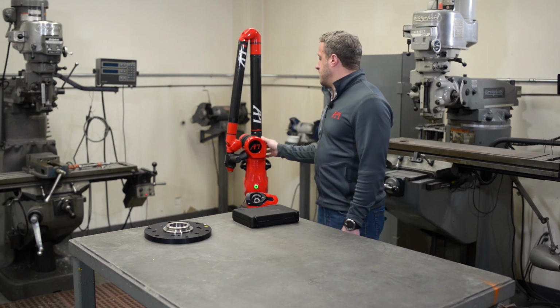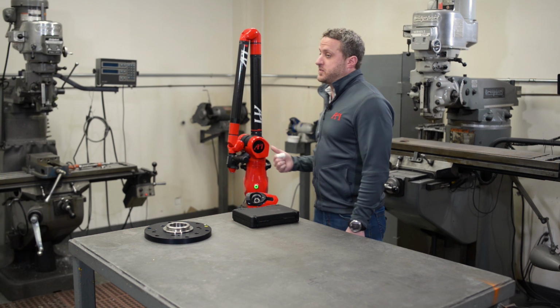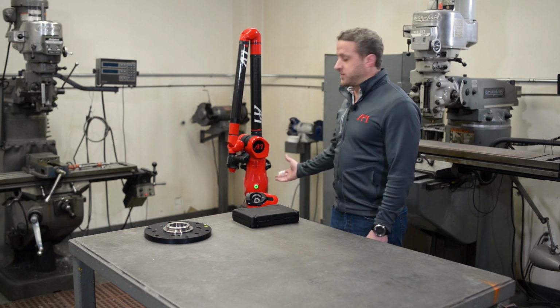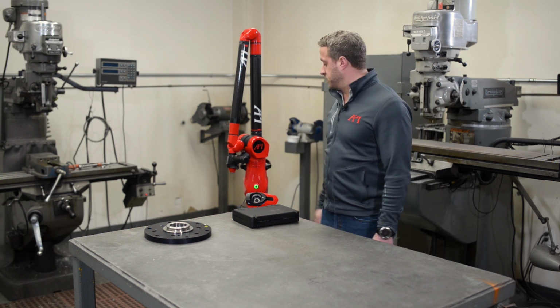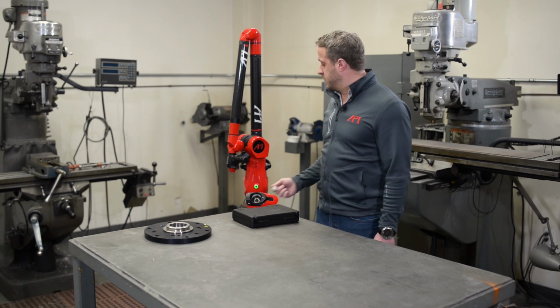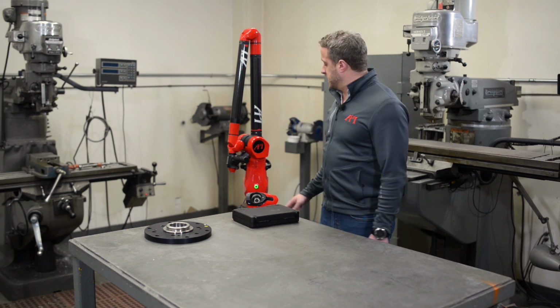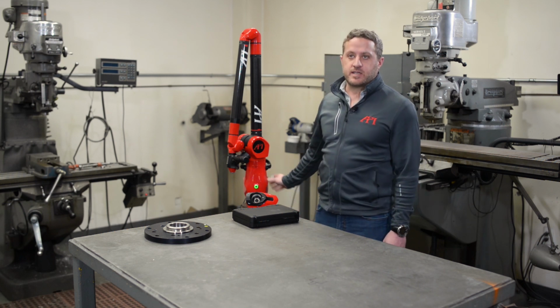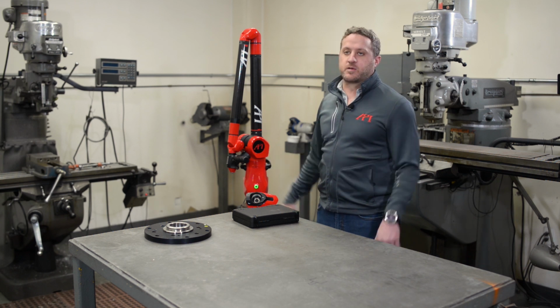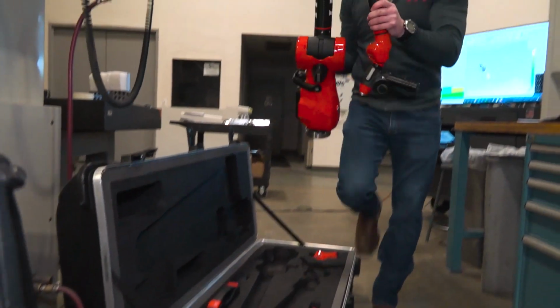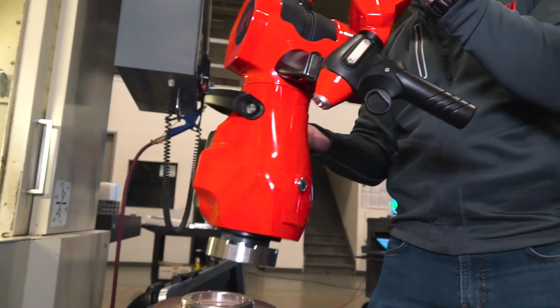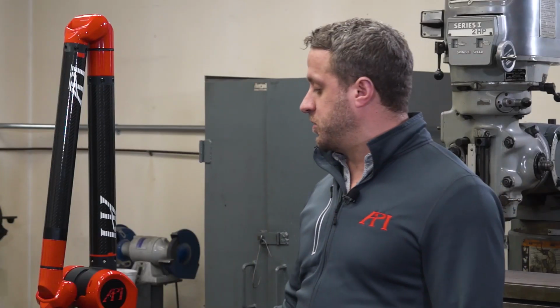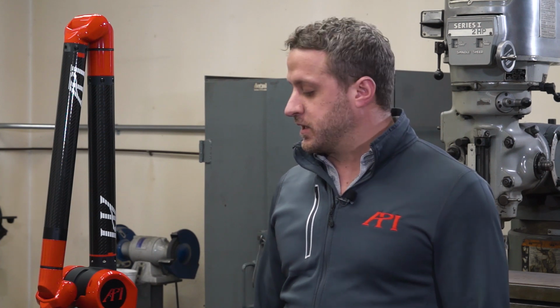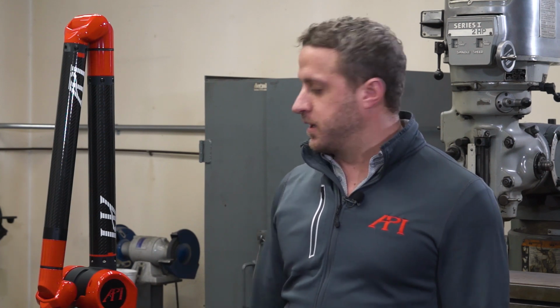This arm has pretty nice features as far as the portability of it. This has a battery pack on the back that can give you several hours of working with no power plugged into it. This also has Wi-Fi capability, so you don't need to be connected whatsoever to the computer to take this into a shop and measure. When the scanner is attached to the arm, we do need to be plugged in through Ethernet, because of the amount of data flow that comes out of the arm, we need that wired connection.